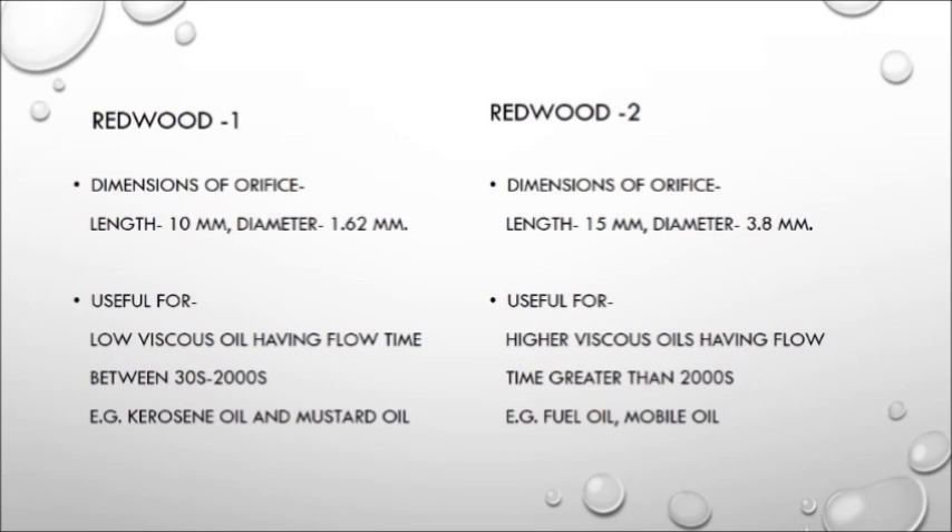Now we will tell you about the differences between the Redwood 1 and Redwood 2 viscometers. The dimensions of the orifice of Redwood 2 are greater than Redwood 1, both in length and diameter. The length of the Redwood 2 orifice is 15 mm, while the length of the Redwood 1 orifice is 10 mm. The diameter is larger in Redwood 2 at 3.8 mm, and the diameter of Redwood 1 is 1.62 mm. Redwood 2 is useful for oils having higher viscosity, for example fuel oil and mobile oil. Redwood 1 is useful for oils having a lower viscosity, between 30 and 2000 seconds, for example kerosene oil and mustard oil.